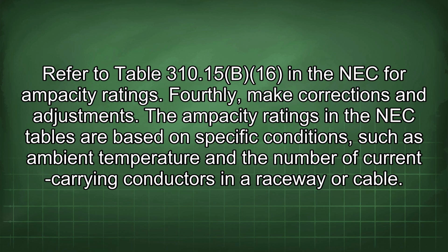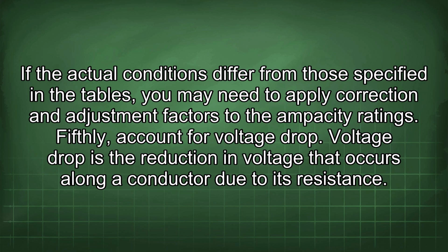Fourthly, make corrections and adjustments. The ampacity ratings in the NEC tables are based on specific conditions such as ambient temperature and the number of current-carrying conductors in a raceway or cable. If the actual conditions differ from those specified in the tables, you may need to apply correction and adjustment factors to the ampacity ratings. Fifthly, account for voltage drop.